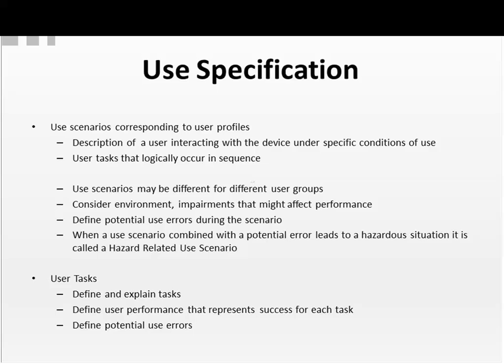We also define the user tasks. We define and explain the tasks. We define the user performance that represents success for each task. And we define the potential use errors in each task. What could the user possibly do wrong in the task?